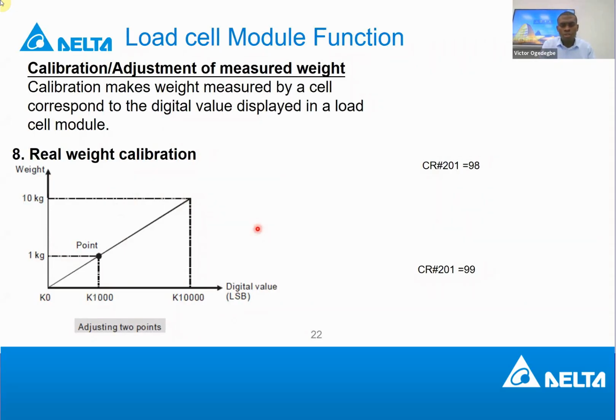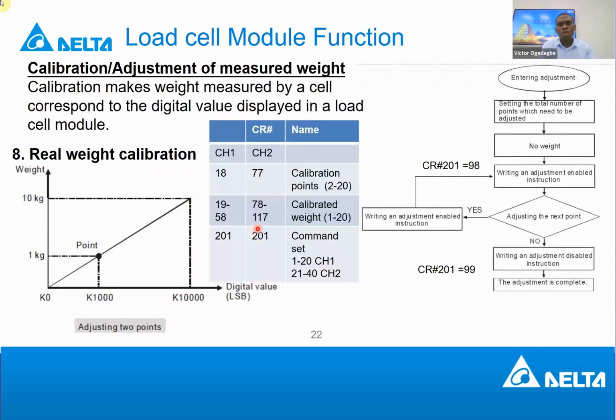There are 2 different types of calibration. The first one is just the real-weight calibration. So this is the flow chart of the calibration. How do you do it? First of all, you can see here it's possible to calibrate 20 points. On this picture, this is 0 point, this is 1 point. So this is 2 point calibration.